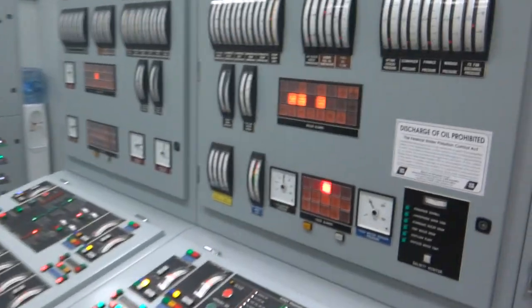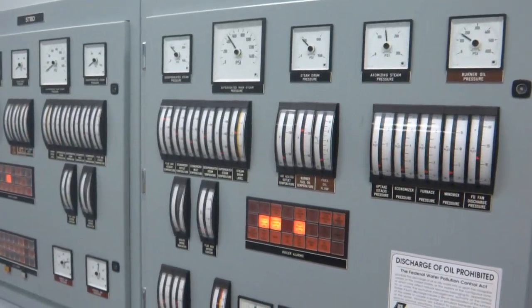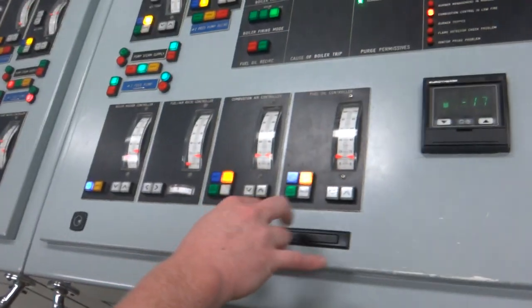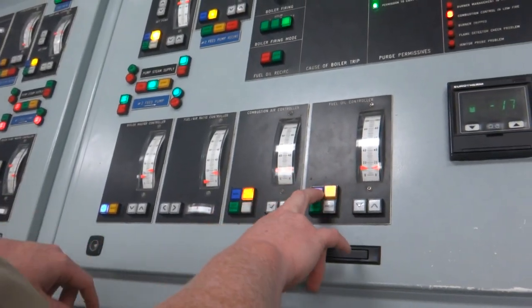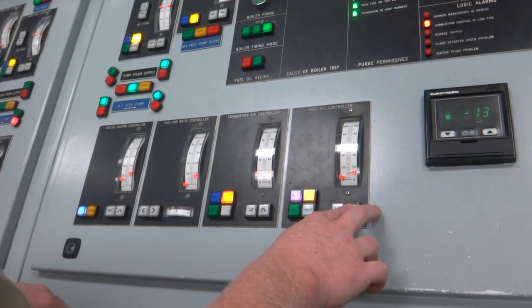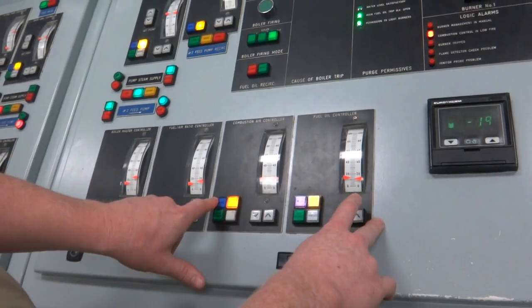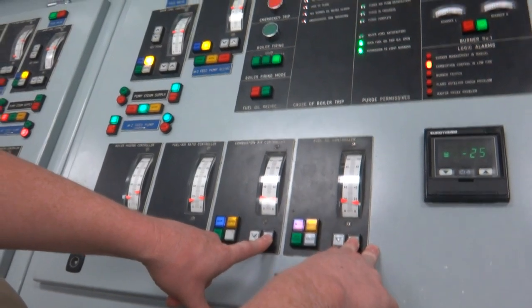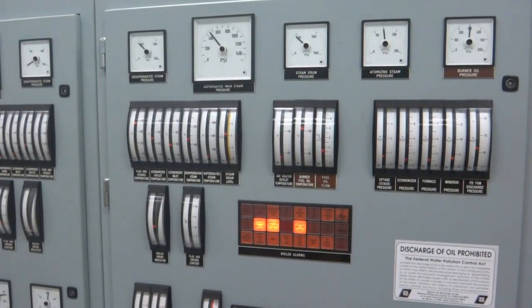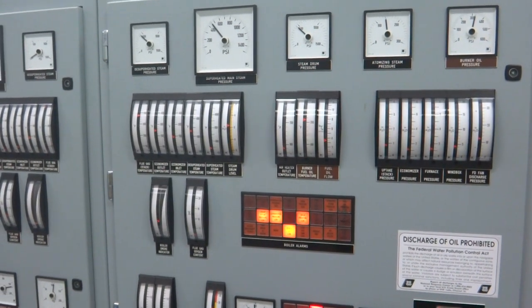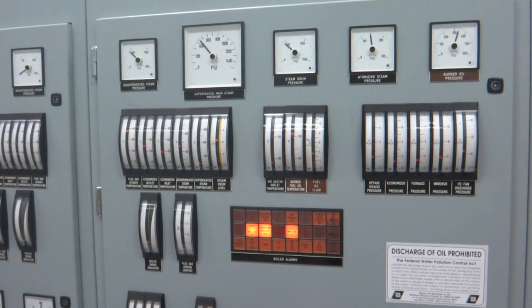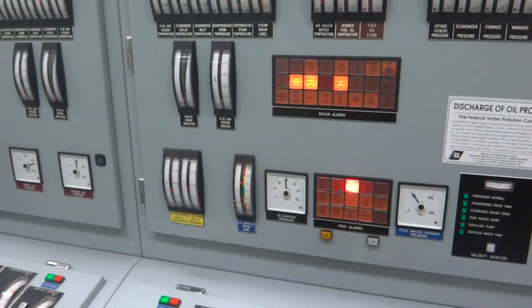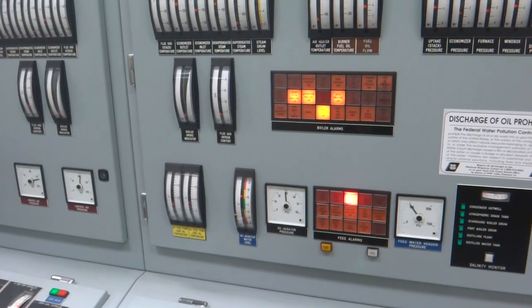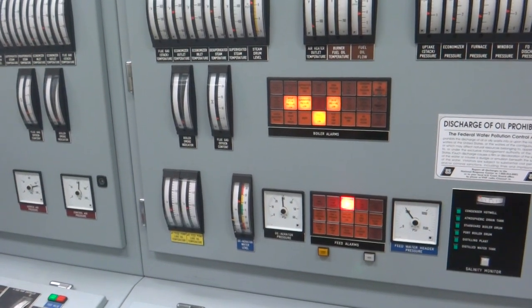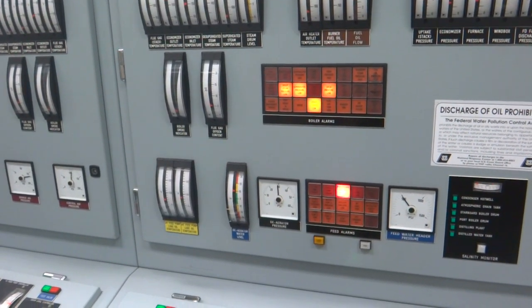Look at your pressure. It's dropping. You better do something about that. Mr. Dackins is our specialist on this. Get it in manual. Look at your fuel pressure. Watch your smoke. Increase the firing rate. All right, your pressure's high enough. I noticed. Succeeded with the smoke. Keep on increasing, or just get rid of the smoke. Okay. Smoke's going. That's as high as you want to go with one burner.